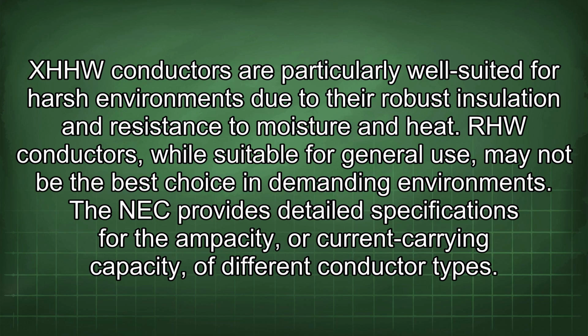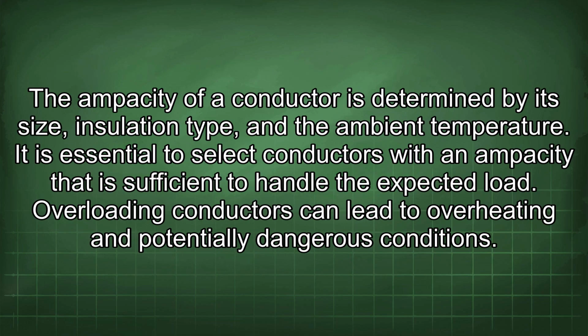The NEC provides detailed specifications for the ampacity, or current carrying capacity, of different conductor types. The ampacity of a conductor is determined by its size, insulation type, and the ambient temperature. It is essential to select conductors with an ampacity that is sufficient to handle the expected load. Overloading conductors can lead to overheating and potentially dangerous conditions.